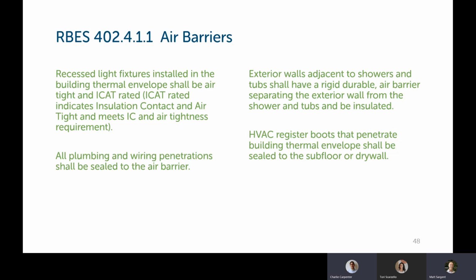I wanted to bring this up in the residential code update. There's air barrier provisions in section 402, and where you may think air barrier provisions would have to do with the building contractor, not necessarily the mechanical contractor, some of the things in there do cross the lines here. So for example, recessed light fixtures have to be ICAT rated. All plumbing and wiring penetrations have to be sealed to the air barrier. Exterior walls adjacent to showers and tubs have to have a rigid, durable air barrier behind them. So yeah, if you're installing a tub on an outside wall and you don't see that air barrier, maybe it makes sense to call that out. Register boots that penetrate the thermal building envelope have to be sealed to either the drywall or the subfloor. So there are some provisions in the air barrier thing that HVAC contractors should be aware of.